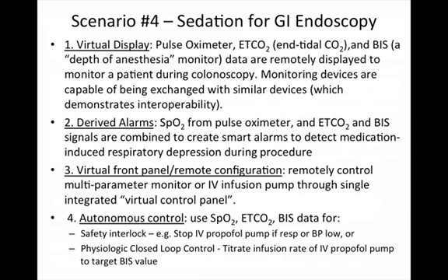So again, in number 2, we are developing derived alarms using data from multiple monitors, using a number of techniques that have been widely published to perform what sometimes is called sensor fusion, or other types of decision support approaches to have earlier detection, a smart alarm with better sensitivity and specificity to detect respiratory depression.